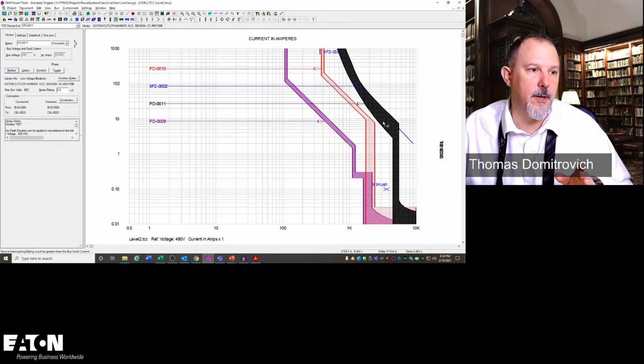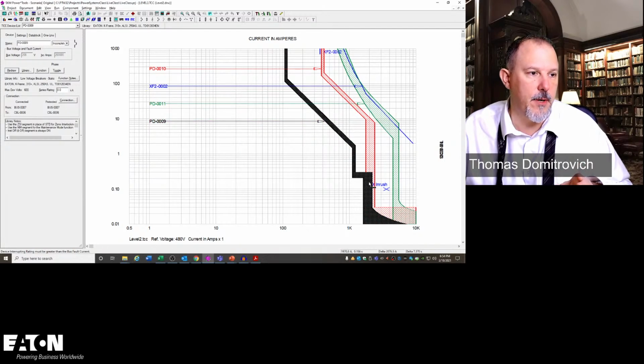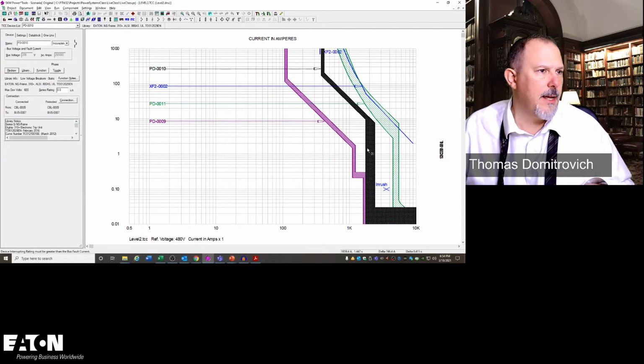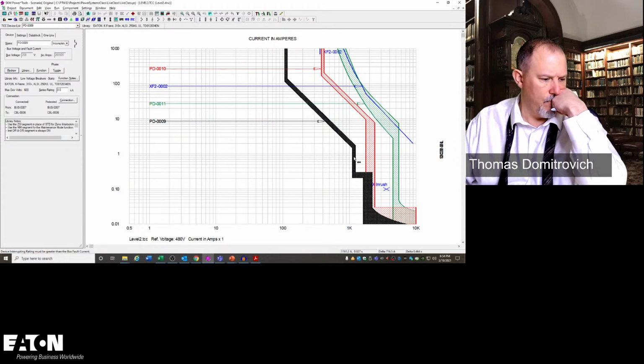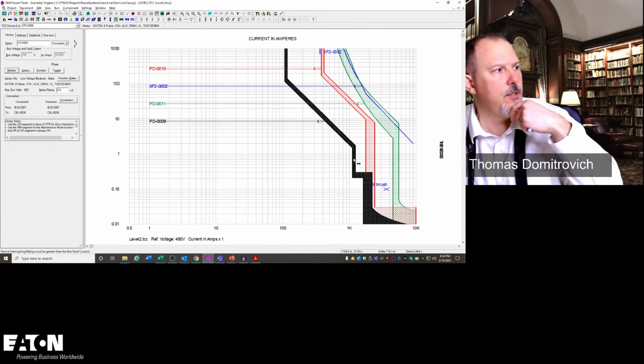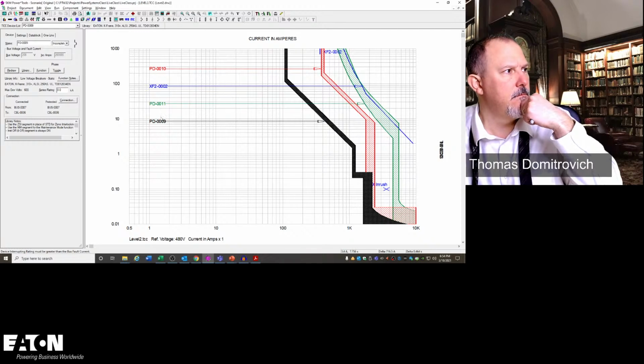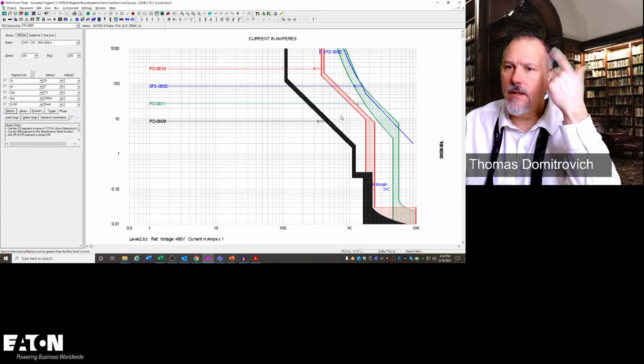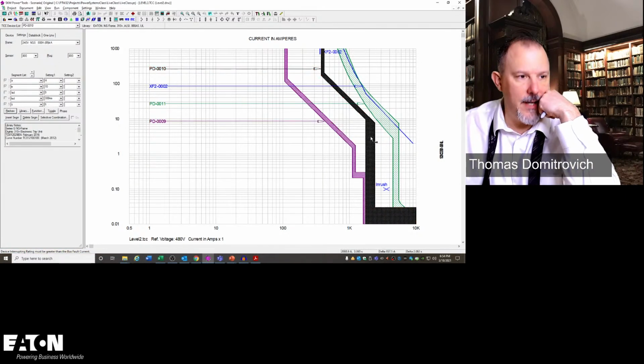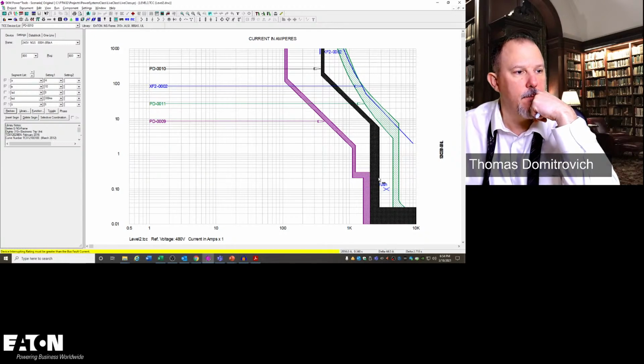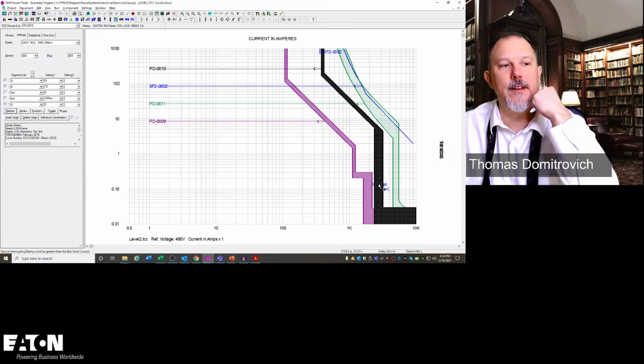Remember, these are the primary and secondary breakers. This is the downstream breaker. And what I'm not liking right now is this is my 225, right? That's my 225. Is it my 225? Settings. That's my 250. It's a 250, right? And this is my 800. But I've got to move, there it is. I've got to move, I need separation.